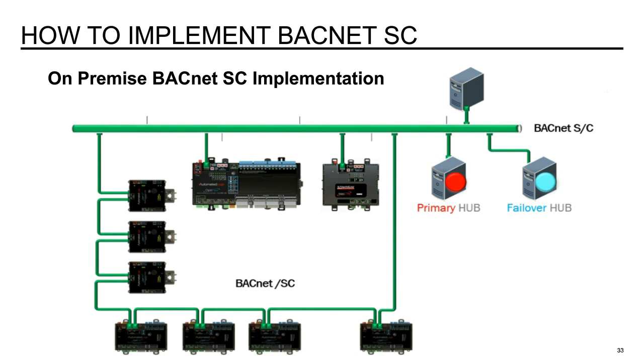And just so you know, BACnet SC, like we mentioned before, is really nothing more than a virtual data link or protocol that talks on an existing IP network. So in an existing installation, or even a new installation, if you're just using Cat6 cable, BACnet SC talks across the Cat6 cable. If you're doing a wireless installation, the BACnet SC protocol is going to be talking across the wireless medium. I just want to point out that there are no physical changes that need to be made to the network media to transmit the BACnet SC protocol.